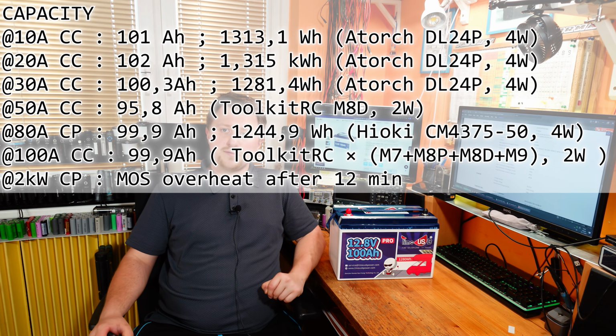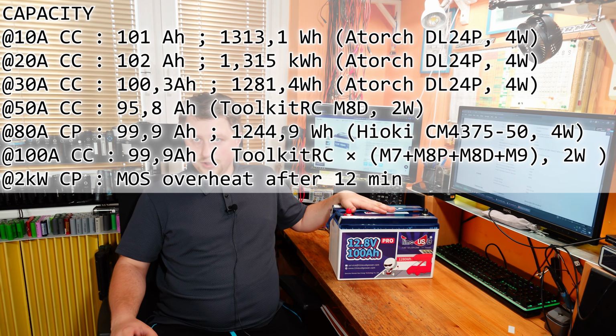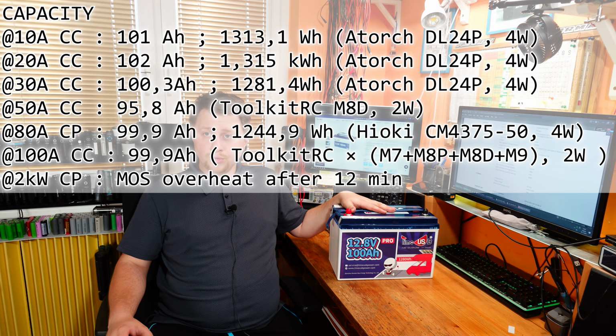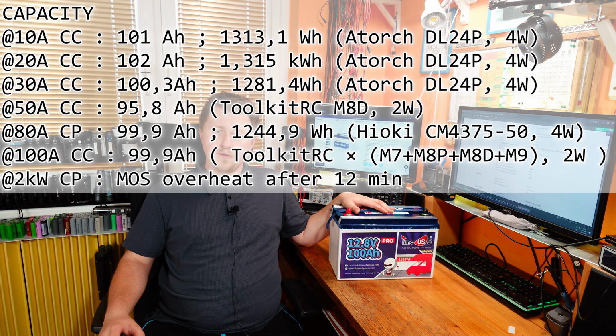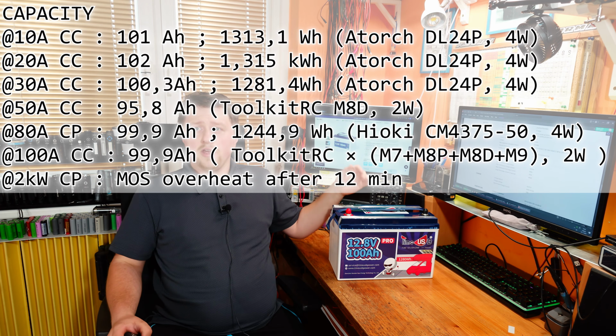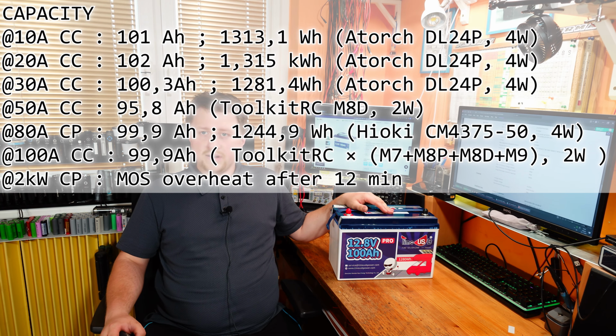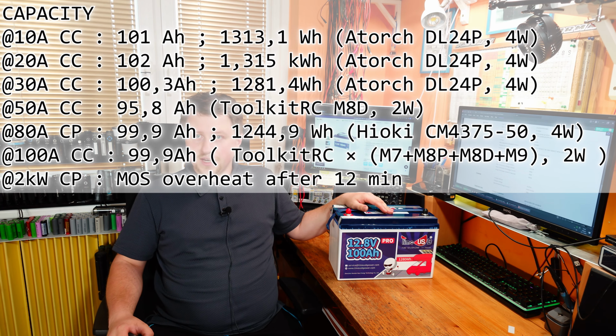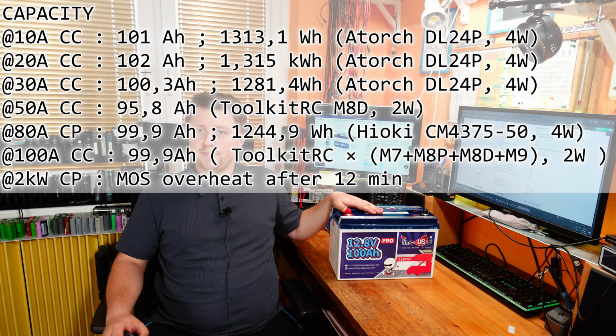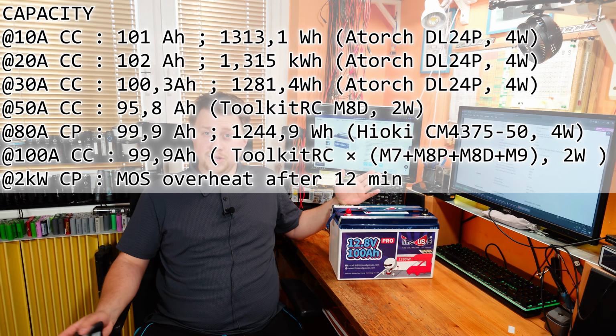All the generated test report data are available in the video description for free download. At 80 amperes load, approximately a 1 kilowatt load, the battery provided 99.9 amp hours and 1244.9 watt hours. If we are at the borderline of the maximum long-term specifications, the battery is still up to the claimed parameters, just 0.1% lower, which is actually nothing.